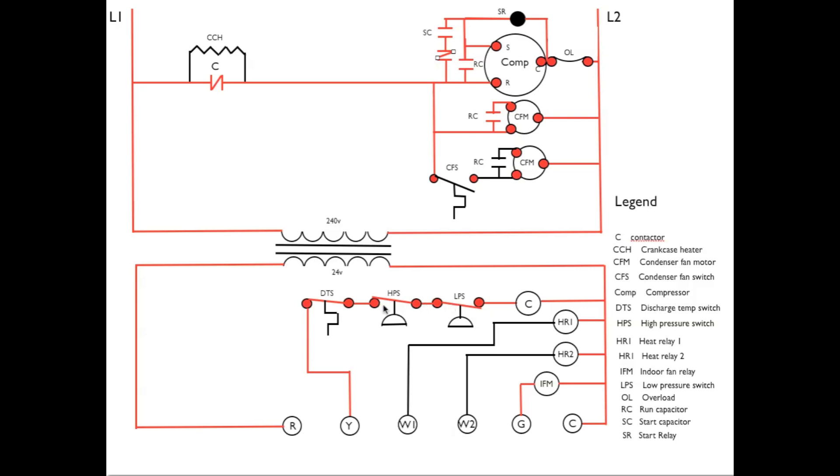These are both refrigerant pressure switches. High pressure switch in case condenser fans fail or something like that, the pressure got too high, it would shut off. And a low pressure switch, if there was a low charge in the system, it would open.